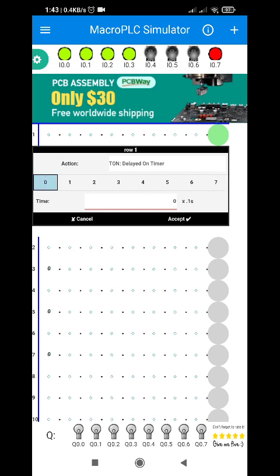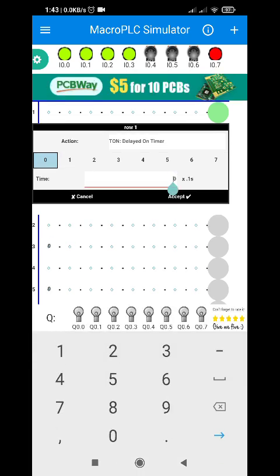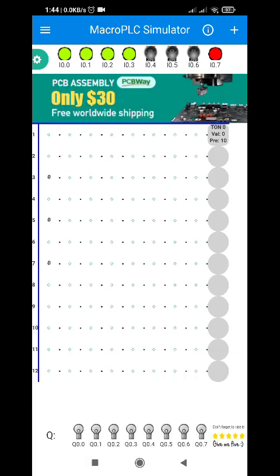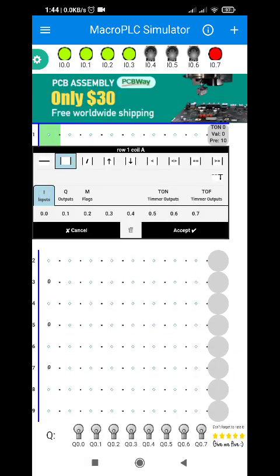We can use up to eight timer relays for Delay ON Timer, but I'm going to use T0, the zero address. This is where we configure or set our time for the timer function. Notice that we have times 0.01 or times 0.1 seconds, so if we put 10 it will be equal to one second only.